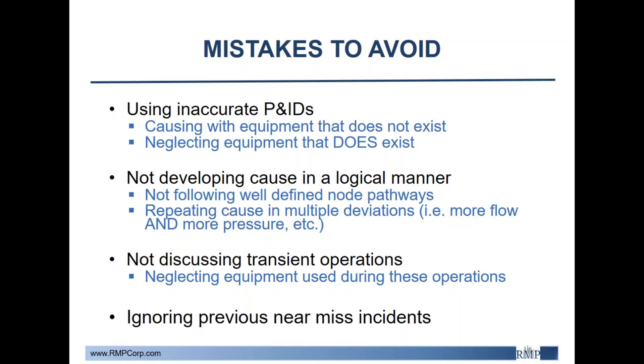Next would be not discussing transient operations. A good number of industry incidents actually occur during these transient operations, so you want to make sure to discuss them. For example, you wouldn't want a valve that is only used during startup or shutdown procedures to be missed simply because it's not considered part of normal operations. Make sure to address any deviations there.